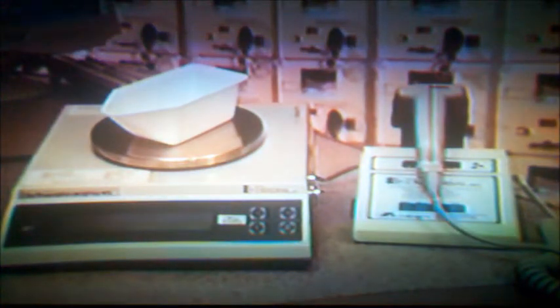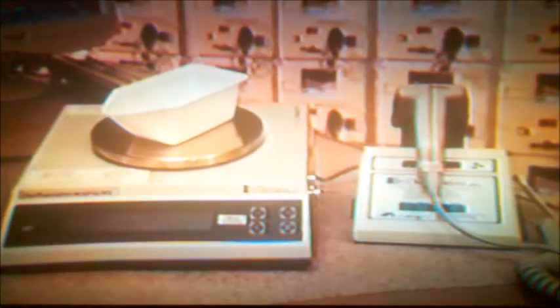Before using your Baker Universal, you will need to do the following. Locate the 2 adjusting feet at the rear outside corners and turn these until the bubble has centered the level, which is on the front left corner of your Baker Universal. Now calibrate the unit. Remove the calibration key from under the lower retaining screw. It is located on the right side of the machine. Also, remove the calibration weight from its box.